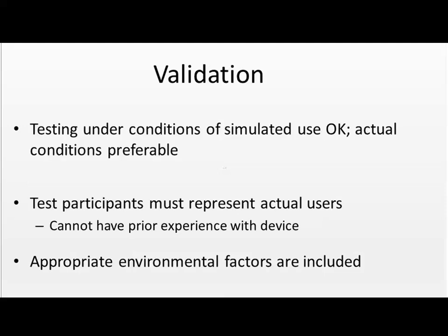Now, the testing under conditions of simulated use is okay, but actual conditions are preferable if it can be accomplished, usually not. The test participants must represent actual users, and they cannot have prior experience with the device. This excludes company employees, even if they fit the profile of a participant. They have some implied knowledge of the device.